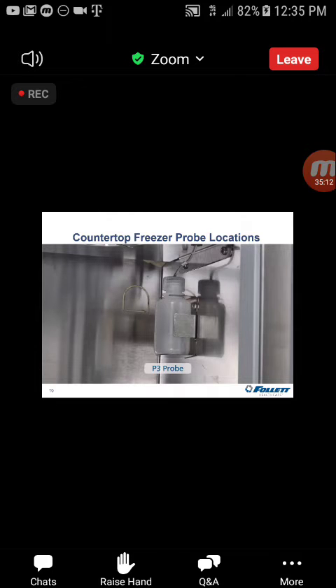The third and final probe, the P3 probe, is our bottle probe. This is the probe located in the product simulation bottle. This is the temperature that is seen on the display of the unit and is used for local and onboard temperature alarming. So there are the probe locations on the countertop freezer.